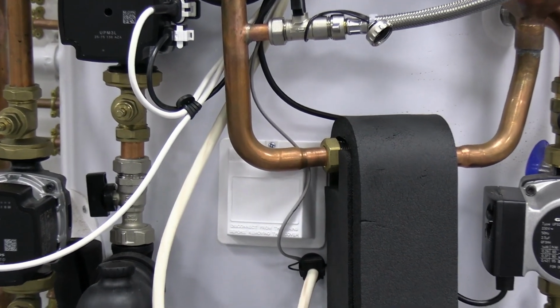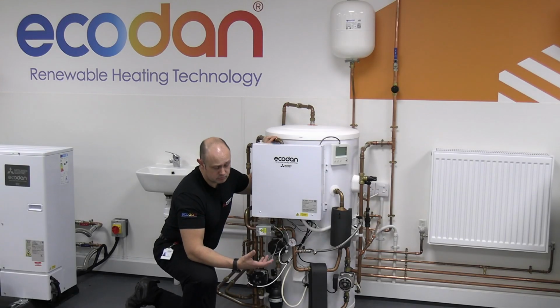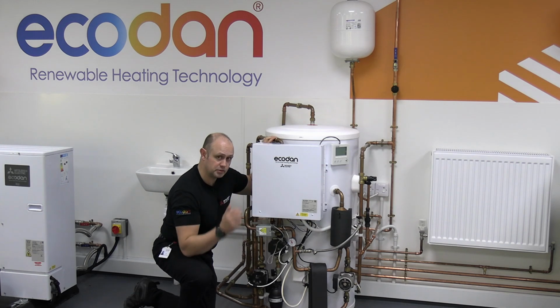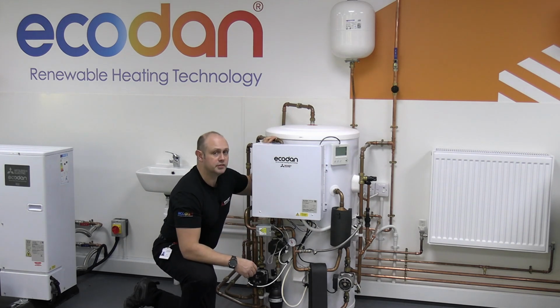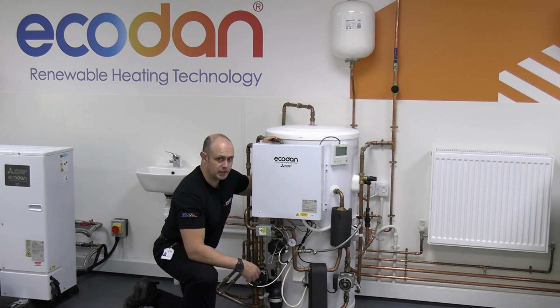The immersion heater is there as a backup, but also more importantly, it's there as the Legionnaires prevention. So the idea being here is once every 10 days, 7 days, 14 days, whatever you want to set it to, we're going to take the cylinder up to 60 degrees and hold it there for maybe up to 5 minutes. Now the actual immersion is L-shaped, so it goes in and goes to the bottom of the cylinder. So by the time that system says it's up to 60 degrees, it is 60 degrees throughout the actual cylinder.